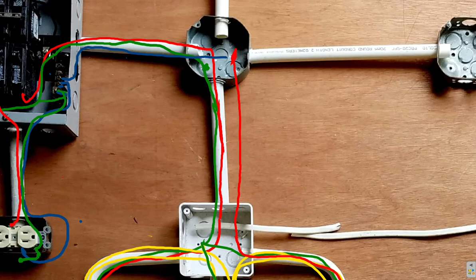You have 3 wires on the photocell: a black, a red, and a white. The black wire is a live wire, and it goes to the line, meaning back to the circuit breaker. The photocell top might show line, load, and neutral. Some say L1 for line, L0 for load, and N for neutral.